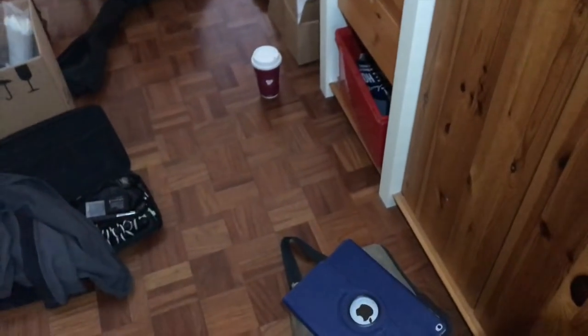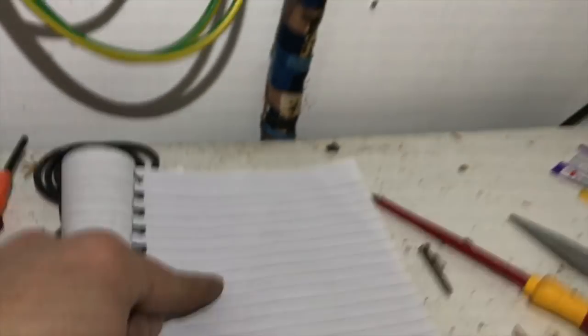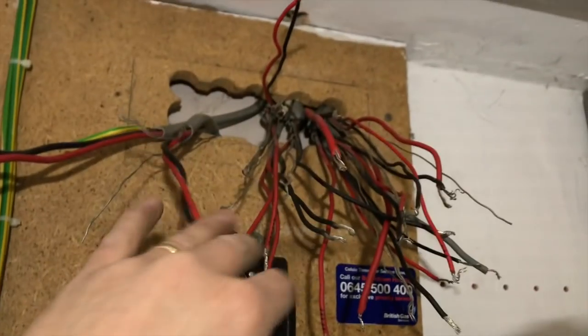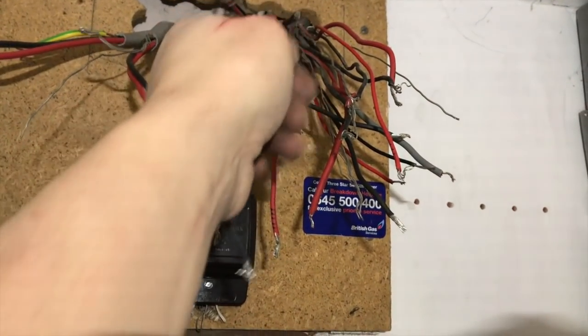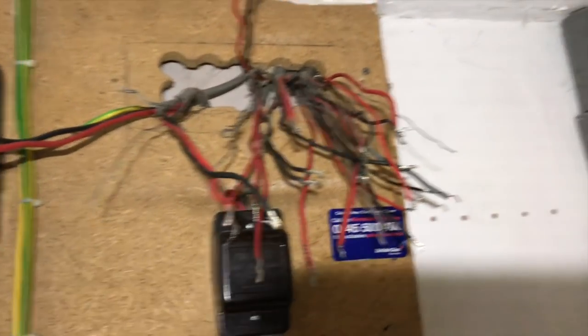I've got my iPad tester in. There's no point in even trying to do it on the iPad yet because we're just doing readings. Just going to get some end to ends and stuff. Let me go around and plug everything, give it a mega 250 first, see what readings we get, and then we can ramp it up to 500 if we're happy. Okay.